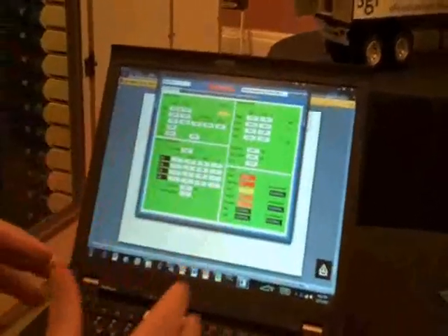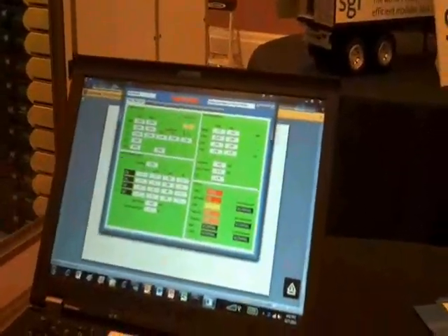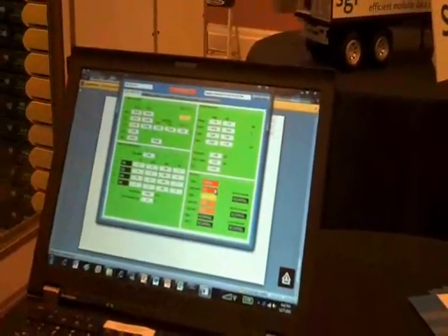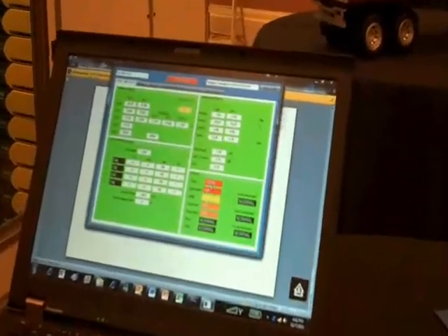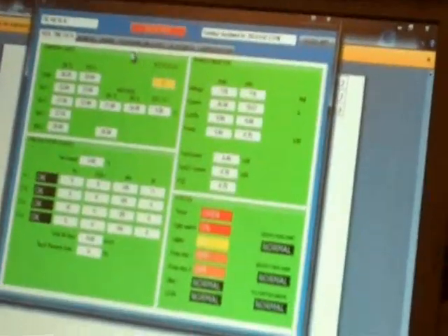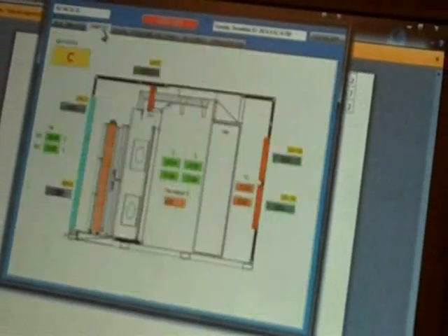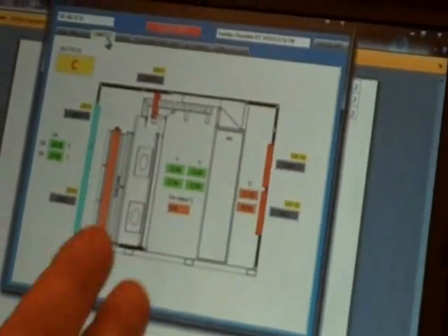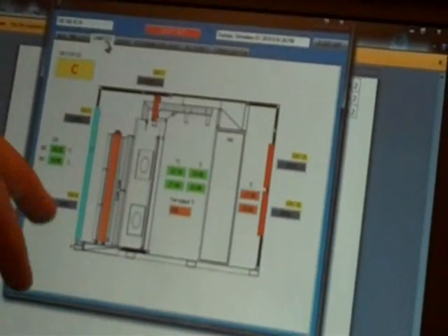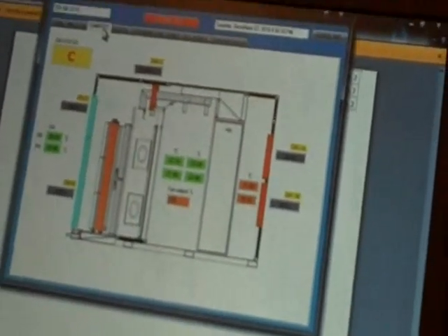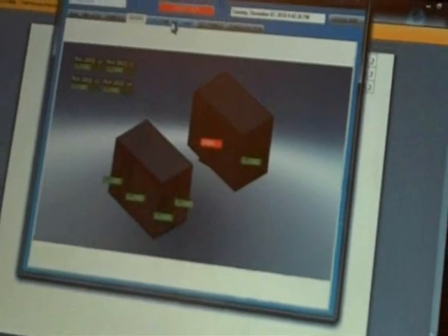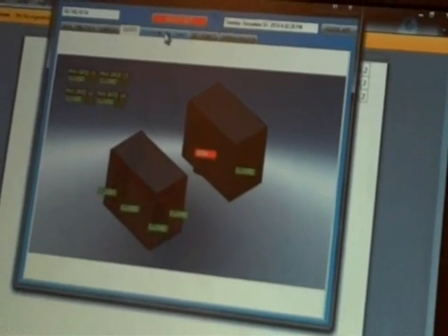What I'm able to do here is constantly monitor the temperature and humidity, outside, inside, and at the inlet to the rack. I'm monitoring the power. I'm monitoring alarms, if the doors are open, if the lights are on, and what state the evaporative media system is in. A little 2D picture helps customers quickly see where the dampers are if you're in a NOC or something like that. And again, simply straightforward, the doors are open or shut. In fact, the door's still open. We should probably shut that.